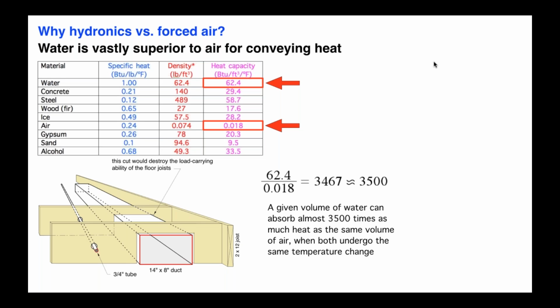For example, here we're looking at 2 equivalent heat transport systems. The one on the left, a 3/4-inch tube, carrying water under normal hydronic design conditions like 4 feet per second flow velocities. And then the duct system, 14 inches wide, 8 inches tall, again, using standard procedures, standard numbers like 1,000 feet per minute for a trunk duct. So that 3/4-inch tube carrying water can convey heat at the same rate as a 14/8 duct carrying air.